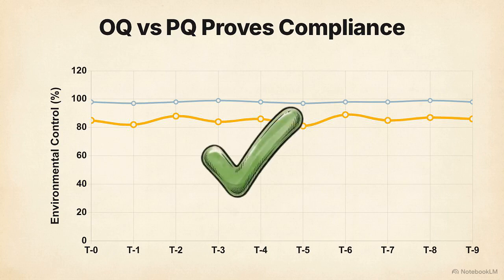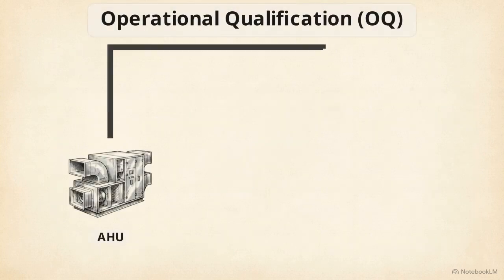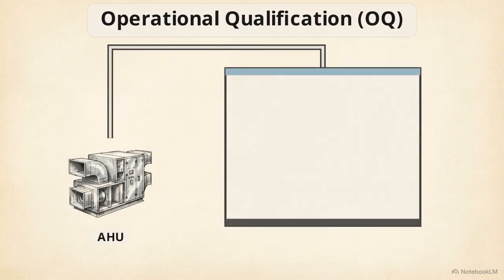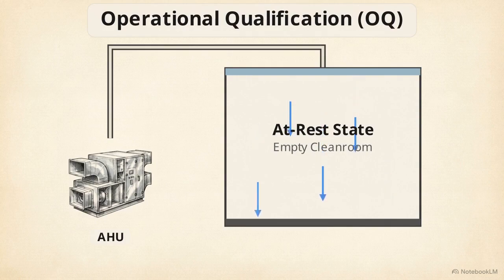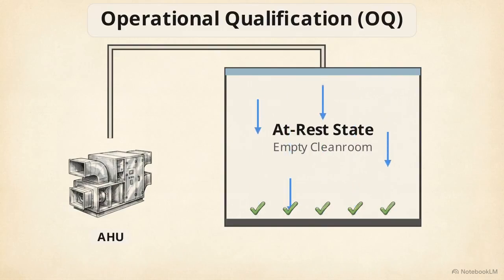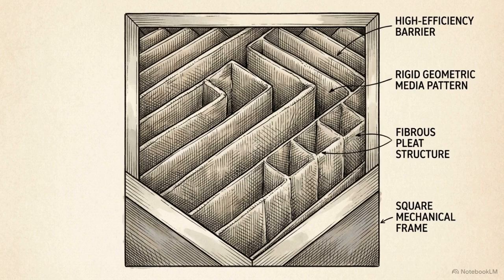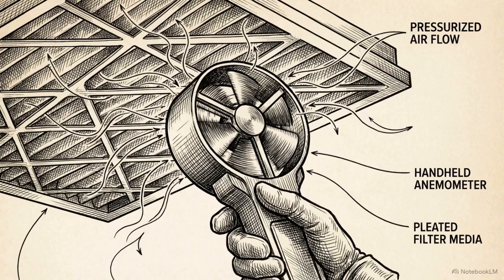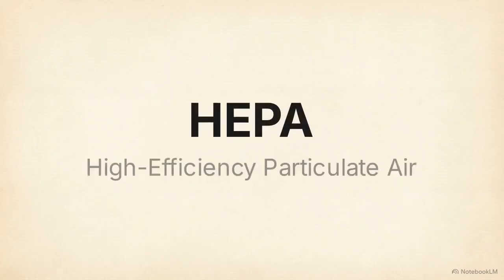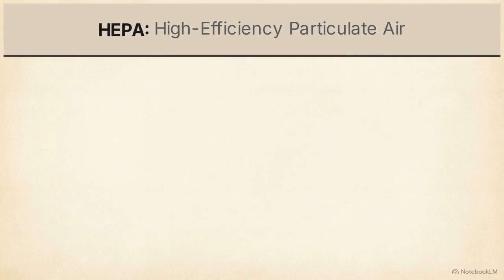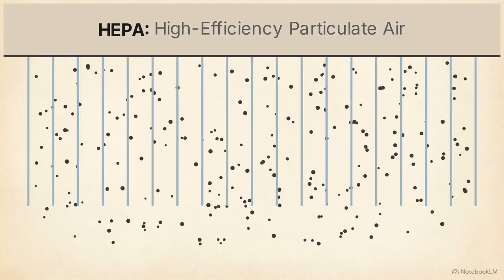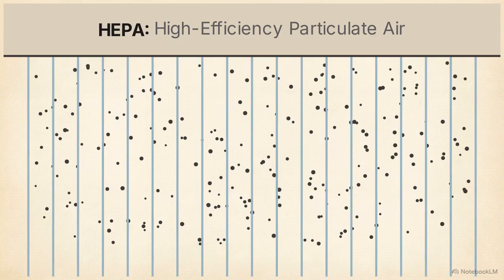a legally compliant cleanroom. Operational qualification is a severe stress test for the HVAC infrastructure. The mandatory condition is the at-rest state. The empty room allows engineers to evaluate the machine in isolation, verifying it maintains functionality at its absolute operational limits. The first critical metric we test is airflow velocity and volume. Engineers measure the speed of the air directly at the face of the HEPA filters. HEPA stands for high-efficiency particulate air, and these physical filters must deliver a strictly uniform volume of clean air to effectively sweep particles out of the room.